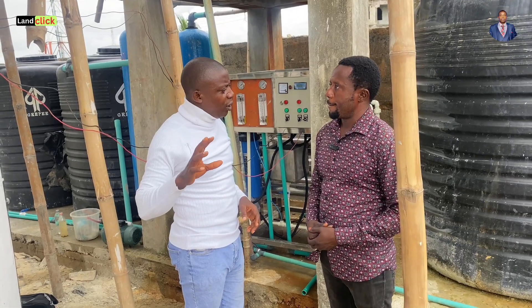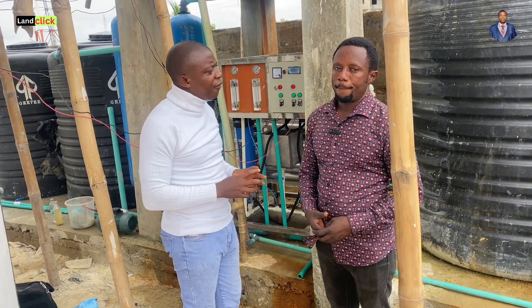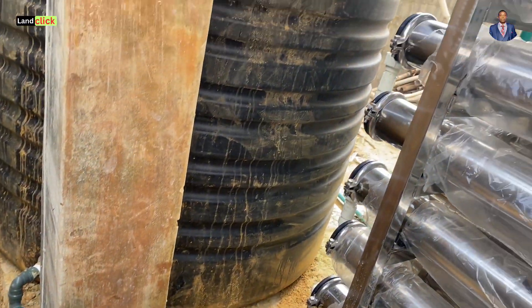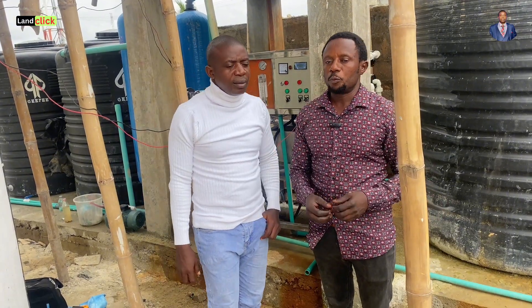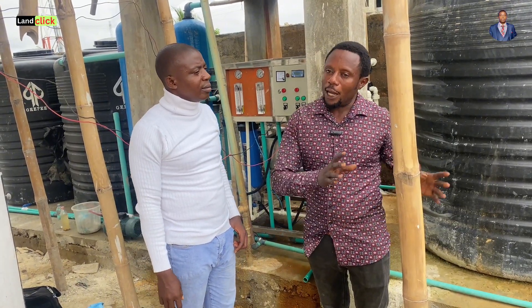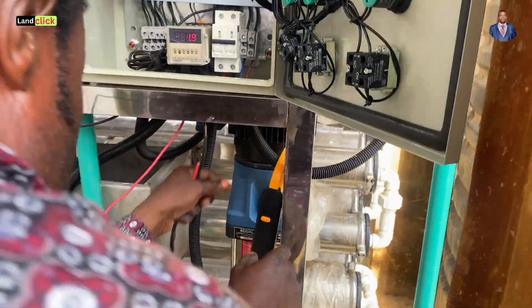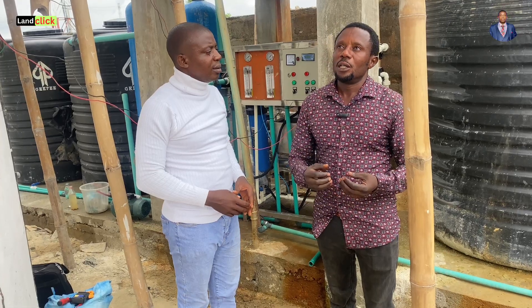Before we jump into the cost analysis — I know you are familiar with Chevron, NERU, IKATI areas — why is it that even though some people have done their water treatment, their water system is still failing and they do not have good water? First of all, as I said, do the analysis of your raw water. By the time you know the chemistry of your raw water, you'll know the kind of treatment and the kind of chemicals you are going to use. A lot of water treatment plants have failed because people are choosing the wrong sequence from another place, thinking the same setup will work somewhere else. If you do your analysis, you'll know the right materials to buy. The operation system may be the same, but the chemicals you need to use are not the same because it depends on the properties of the raw water.